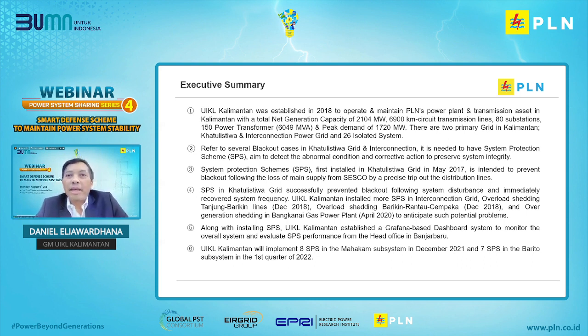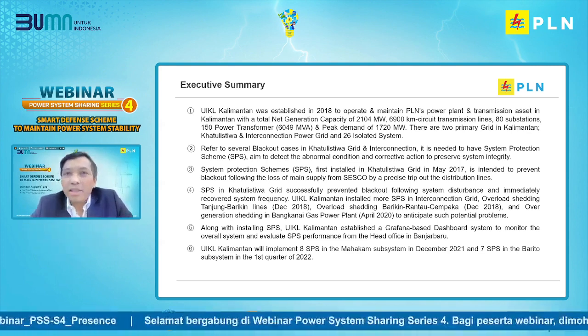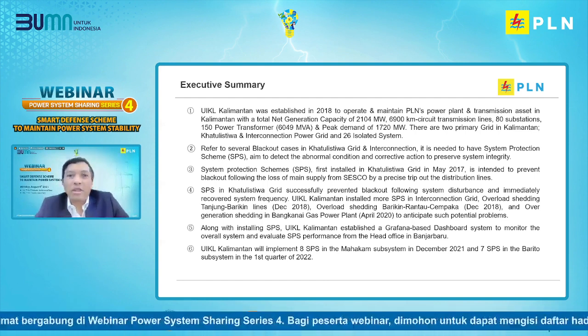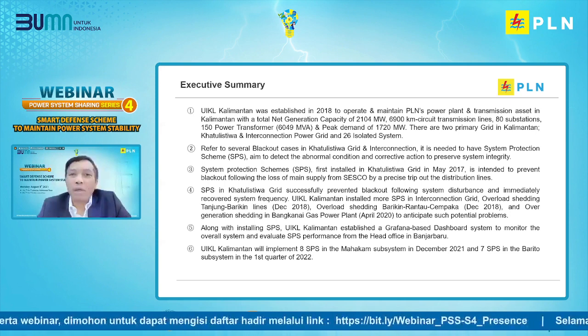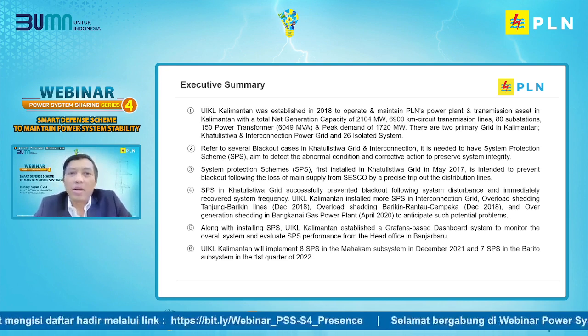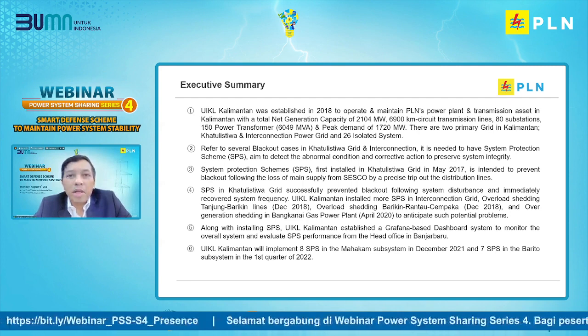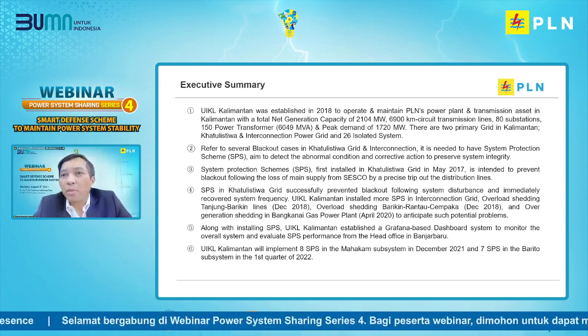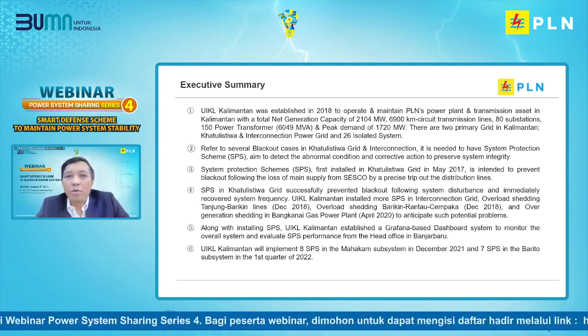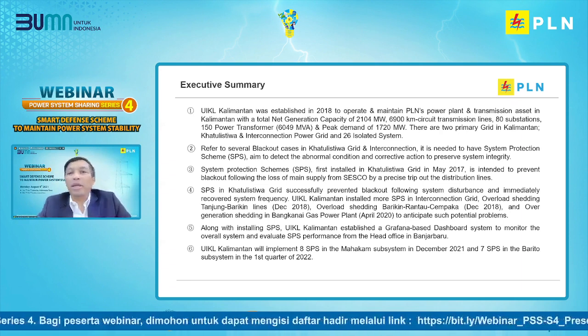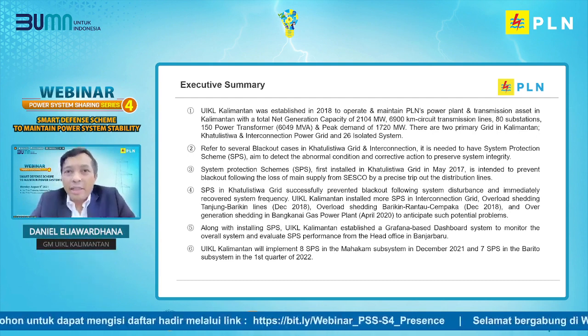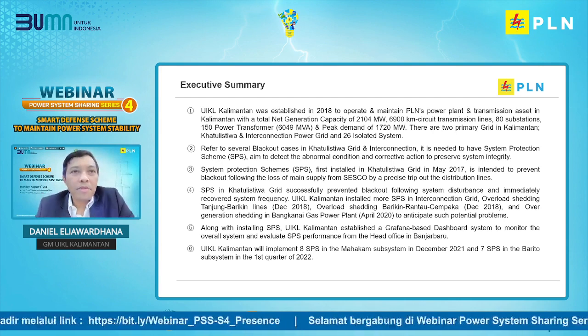The main reason for implementing SPS in 2017 is to avoid blackout and immediately recover system to normal condition. And the SPS successfully prevents some blackouts that potentially occur following major system disturbance. After being installed in Khatulistiwa grid, the SPS was also installed in the Mahakam and Barito subsystem, as well as in Bangkanai power plant. SPS is designed to work properly, adapting to the current system condition, to anticipate several possible events according to system requirement or network topology. To monitor the performance of SPS, we established Grafana-based dashboard system in PLN headquarters in Banjarbaru, South Kalimantan. In the future, we plan to install more SPS in Kalimantan, where 8 SPS in Mahakam subsystem and 7 SPS in Barito subsystem.